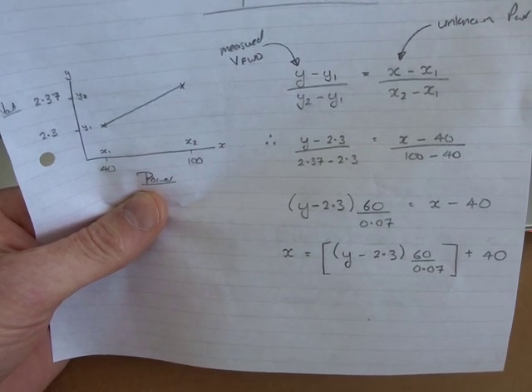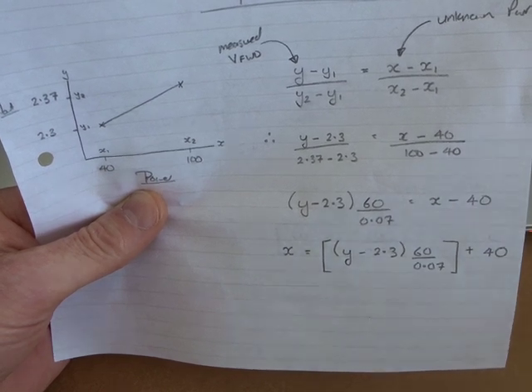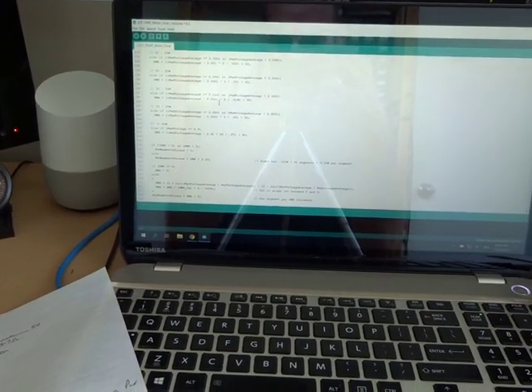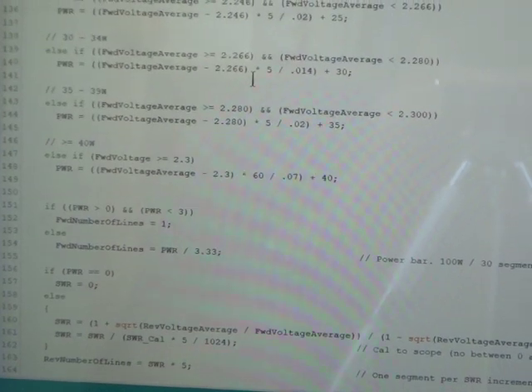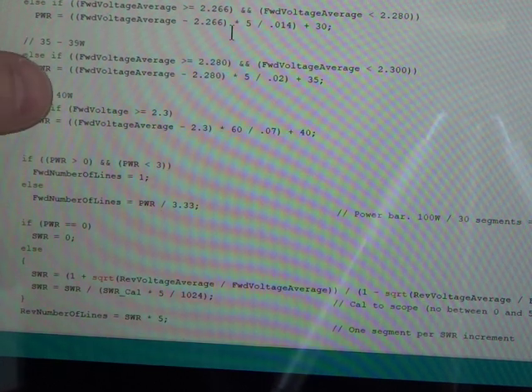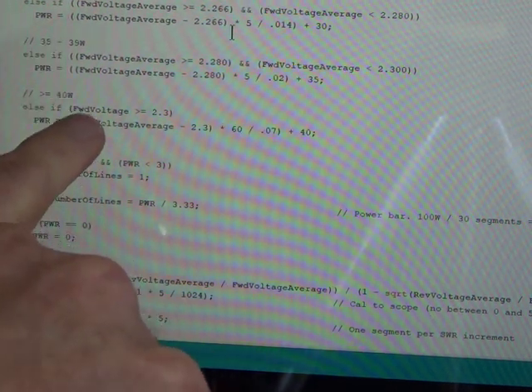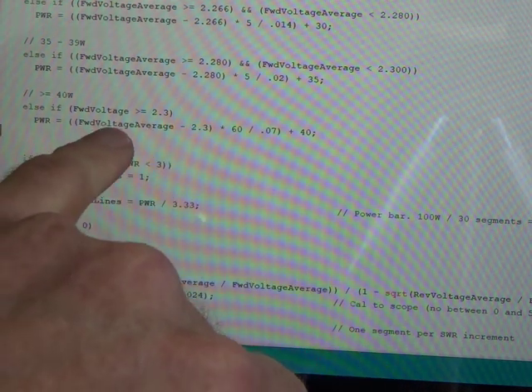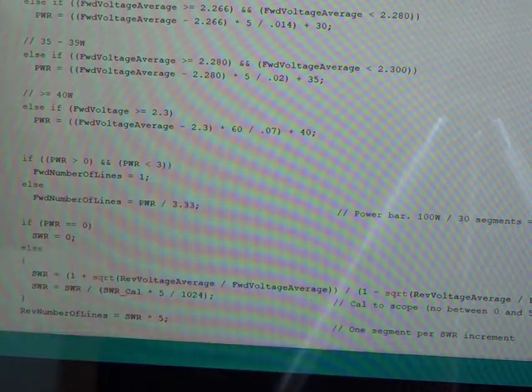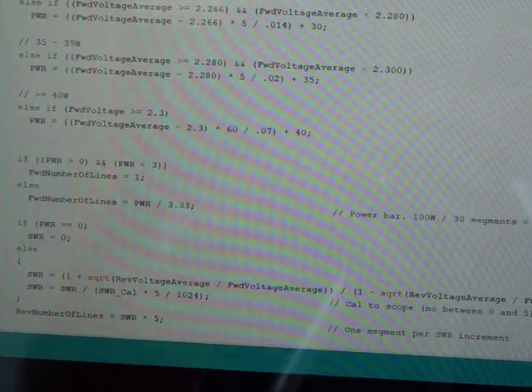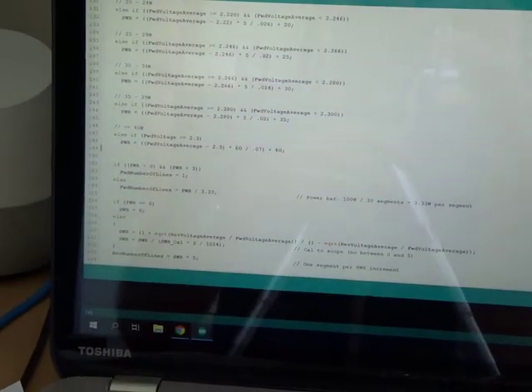So if I was just to jump up into our program, and if I just move that up to there, we can see there, let me just zoom up a little bit. Sorry about that. That's exactly what we see here. So in our lookup table, anything greater than 40 watts, in other words the voltage is greater than or equal to 2.3, that's our function. So our y, our measured voltage, minus 2.3 times 60 divided by 0.07 plus 40 gives us our power, and that's what we're actually displaying on the display.